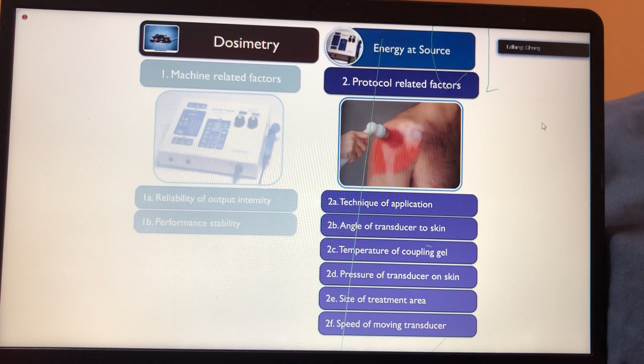So if you demand that your ultrasound device must be at least not really calibrated, but doing this calibration graph that you're doing, you're not doing anything to the internal parts of the ultrasound. You're just finding out what is the power meter display and what's the ultrasound display, print it out, and then you read off the graph to get what you want. The protocol related factors are perhaps more easy. I didn't need to answer most of it. There are 2 that I need to answer, but technique of application, I know most of you do.